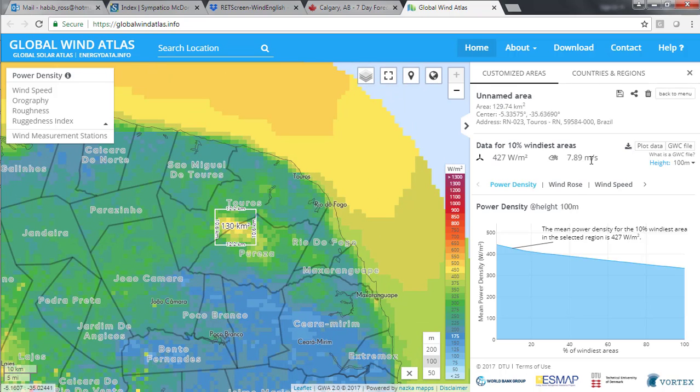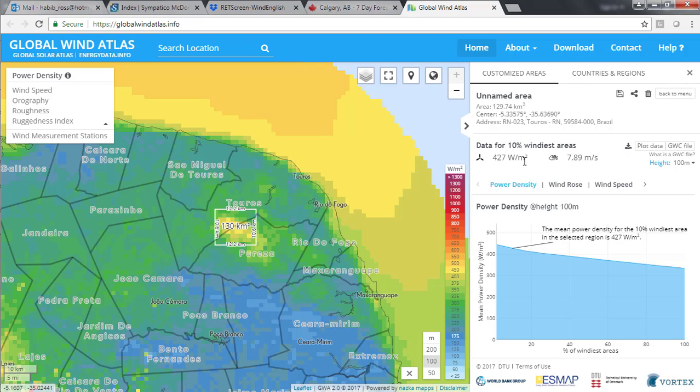This is only 12% lower than St. Lawrence. But remember, the power in the wind varies with the cube of its speed. The wind power density, or how much power is available from a one square metre area in the plane of the turbine rotor, is around 430 watts per square metre, nearly 50% lower than the 840 watts per square metre available at St. Lawrence.